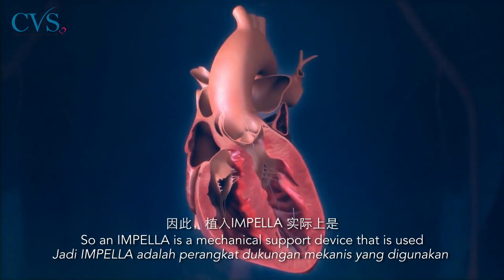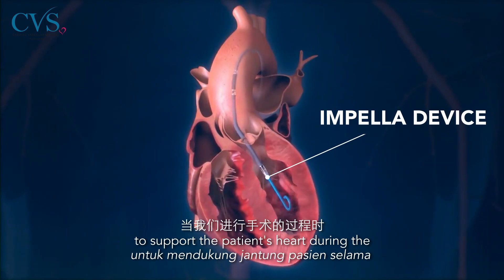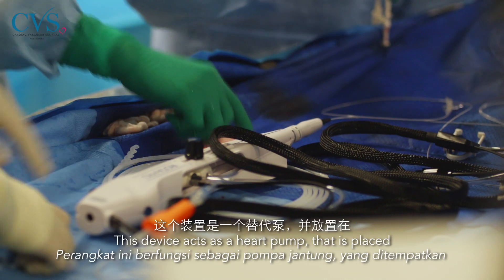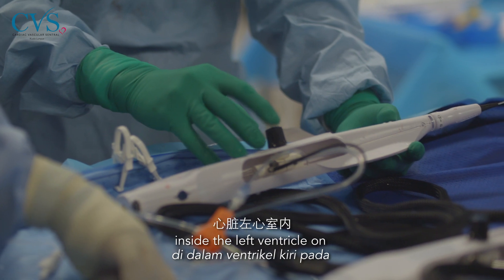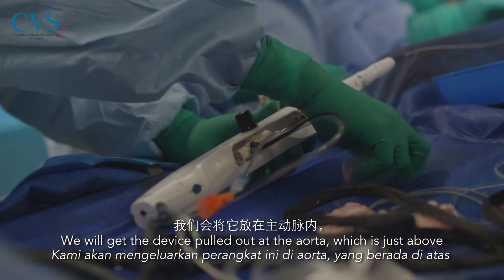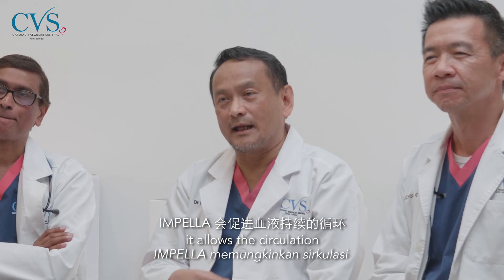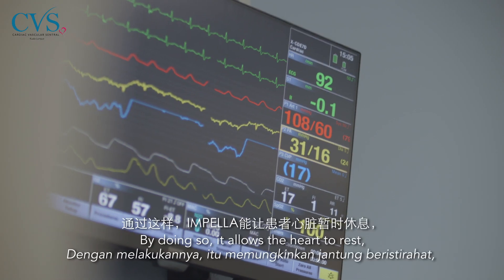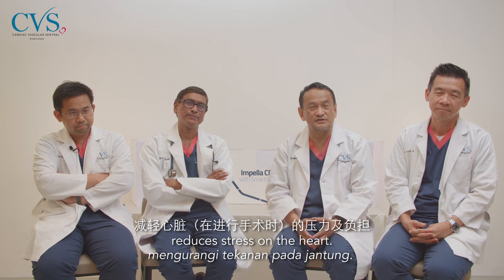An Impella device is a mechanical support device used to support the patient's heart during procedures. It is a pump placed inside the left ventricle, or the left side of the heart, with the outlet in the aorta just above the aortic valve. In this way, it allows circulation of the blood to continue, resting and offloading the heart and reducing stress on it.